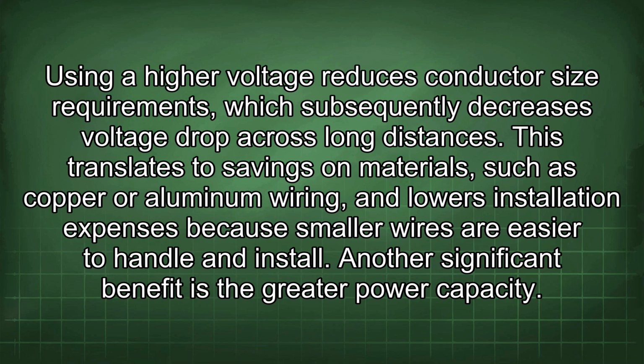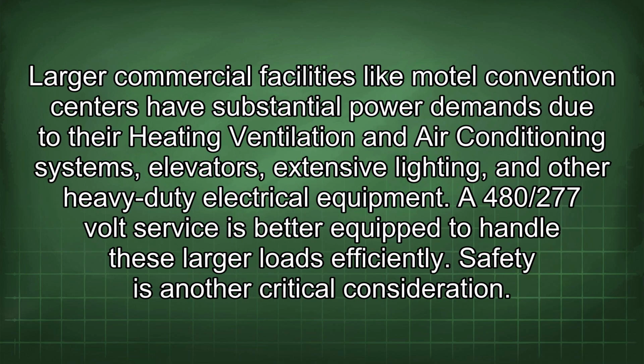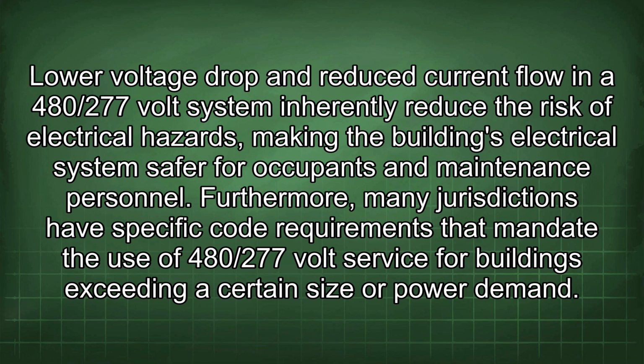Another significant benefit is the greater power capacity. Larger commercial facilities like motel convention centers have substantial power demands due to their heating, ventilation and air conditioning systems, elevators, extensive lighting, and other heavy-duty electrical equipment. A 480/277 volt service is better equipped to handle these larger loads efficiently. Safety is another critical consideration. Low voltage drop and reduced current flow in a 480/277 volt system inherently reduce the risk of electrical hazards, making the building's electrical system safer for occupants and maintenance personnel.